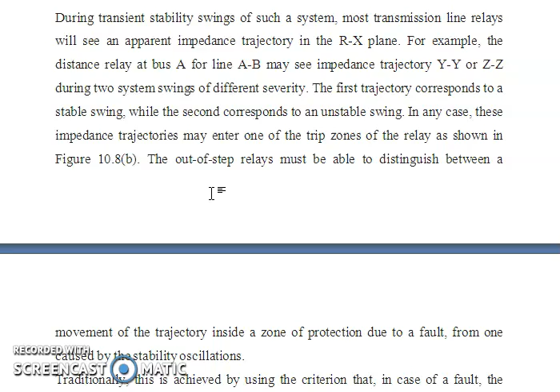Now these are for two different system swings of different severity. The first trajectory, YY, corresponds to a stable swing, while the second corresponds to an unstable swing. In any case, this impedance trajectory may enter one of the trip zones of the relay as shown in the figure. Now the out-of-step relays must be able to distinguish between the movement of the trajectory inside a zone of protection due to a fault and one caused by stability oscillations. Traditionally, how can it be identified? In case of a fault, the trajectory moves very quickly, while a stable oscillation creates a slow movement in the Rx plane.